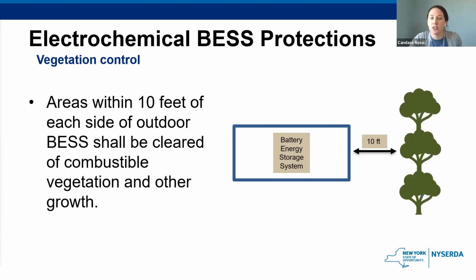So here we have the vegetation control. So 10-foot distance is needed for all vegetation except ground cover, such as grass. This is to prevent a fire from spreading to different locations outside the enclosure. And once again, it's actually allowed for reduced clearance to combustible vegetation shall be permitted based on large-scale fire testing. I assume that won't happen very often, as 10 feet seems to be a sufficient setback that projects will be able to meet. And also separately, depending if you have a local law, you might have other setbacks in there that they'll also have to take into consideration.